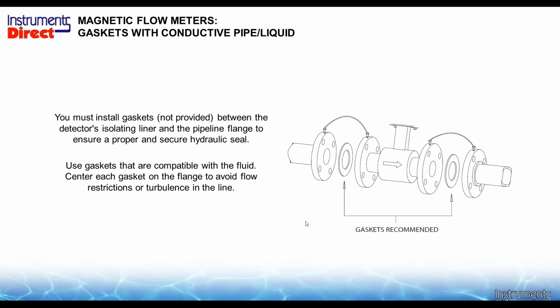Now, plumbing this device into your existing hardware configuration. This configuration comes with a 150-pound flange. So to install this device from flange to flange, you do need a mating flange and a gasket. The gasket is not provided with this device because there are all different kinds of gaskets, and we can make a suggestion. You can just go to Grainger to get something like that, or you'll have your own fittings.